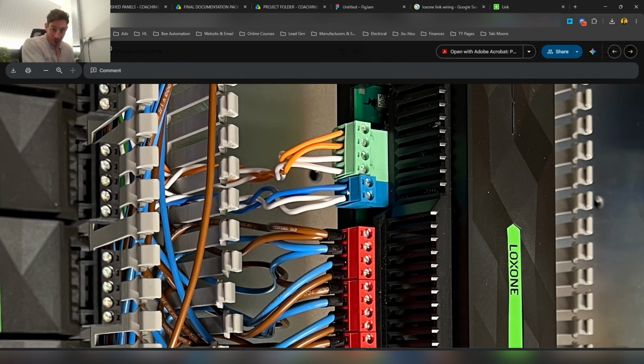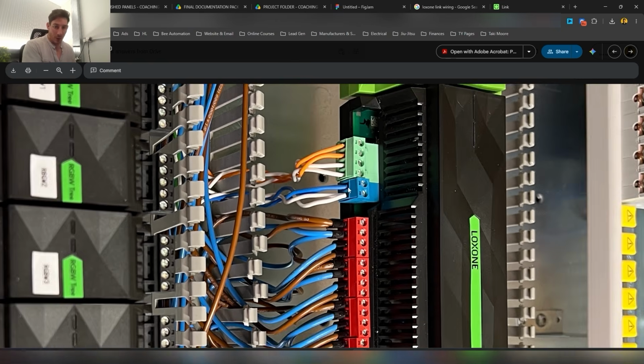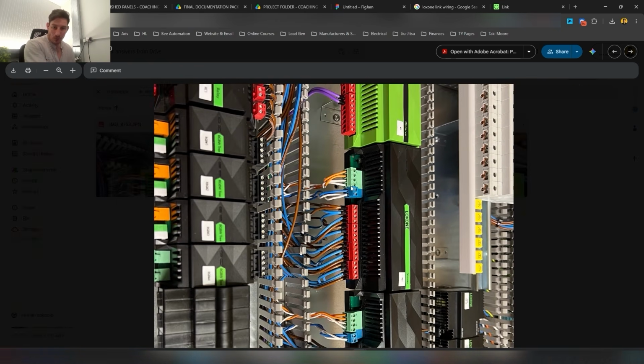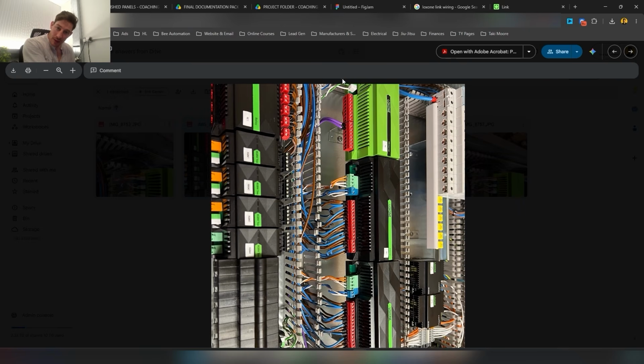So as you can see, I've been very specific with the length I strip it back. I always test it - I set my cable strippers, I strip it back, I put it in the terminal, and then I look at, is that enough? Is that too much? Is that too little? And if it's okay, great, I can do all the others. But always check it first time around. Anyway, off on a bit of a tangent there.